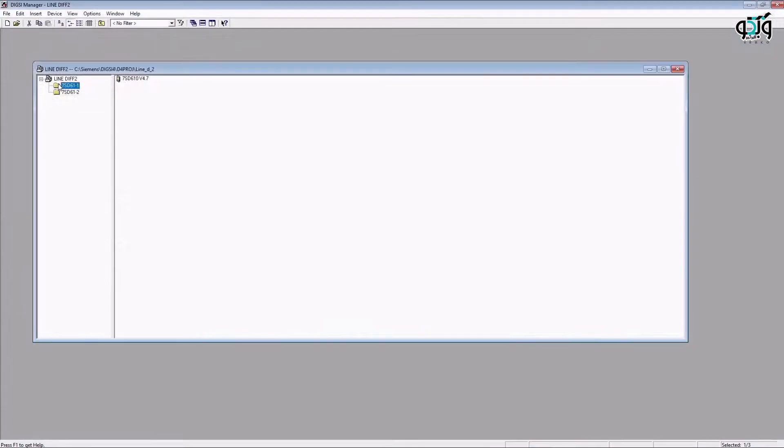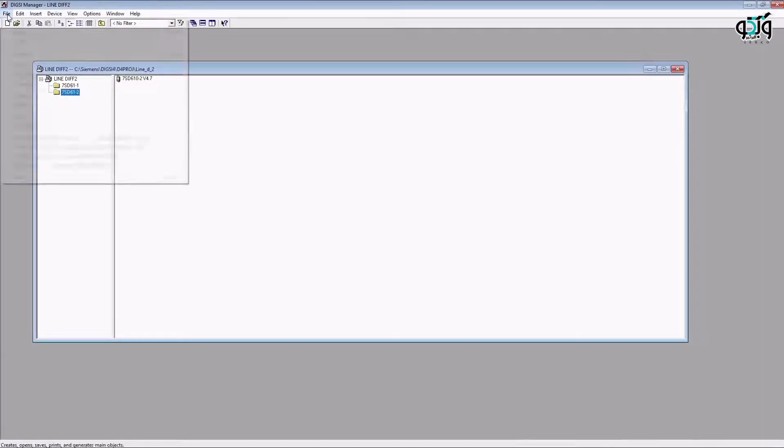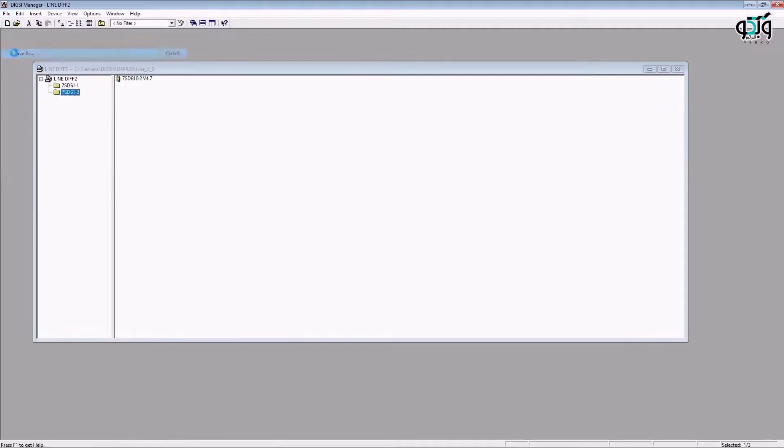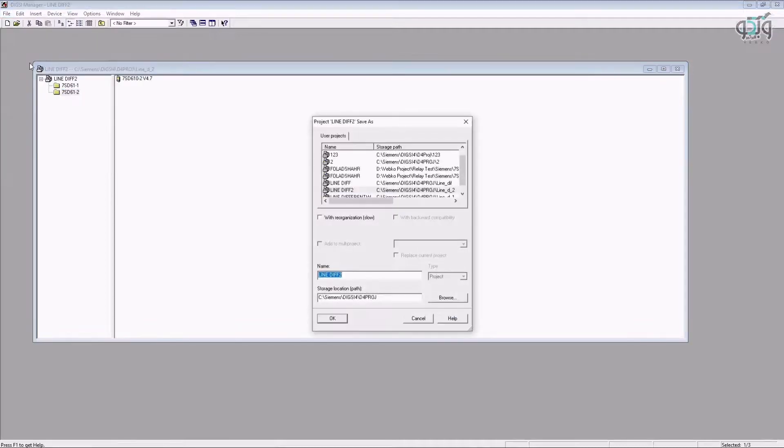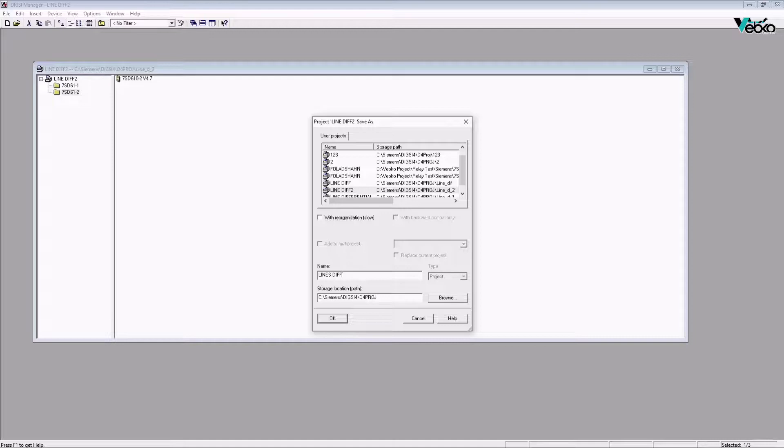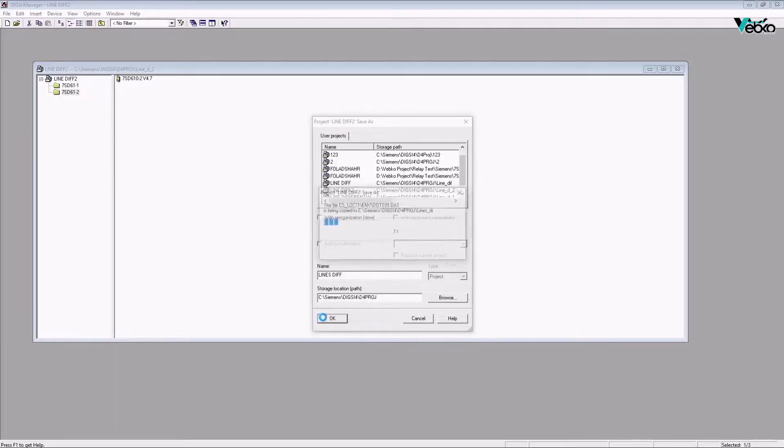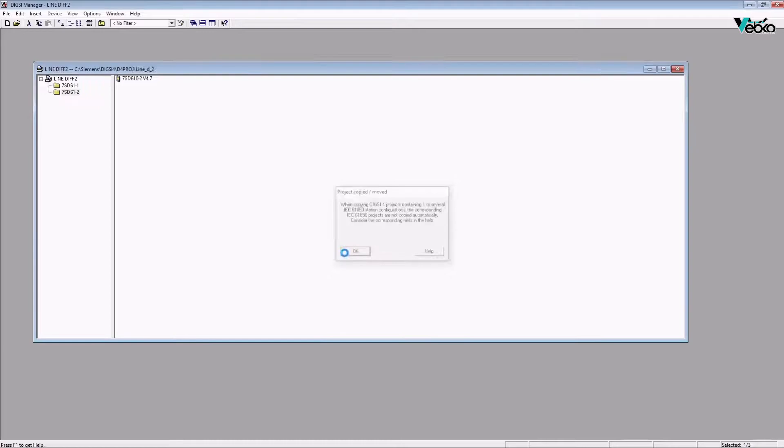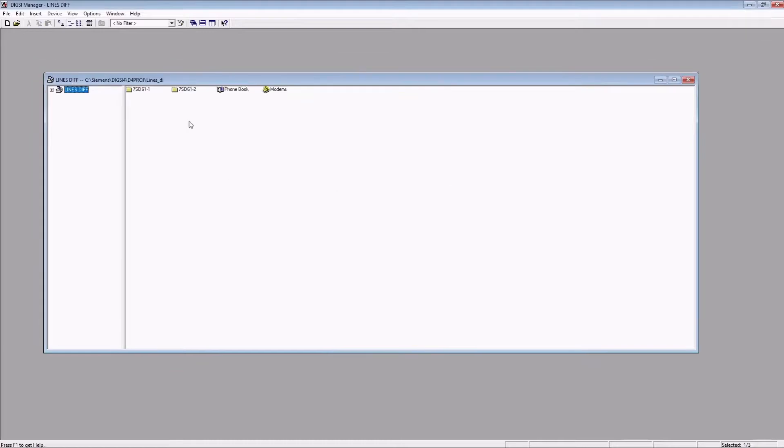In the software section, before anything, it is necessary to connect to the relay and save setting and config files as well as the records submitted for event and disturbance somewhere safe so that if there is a problem, they can be used as a backup. In the next step, export the file needed to enter the test device from the relay.